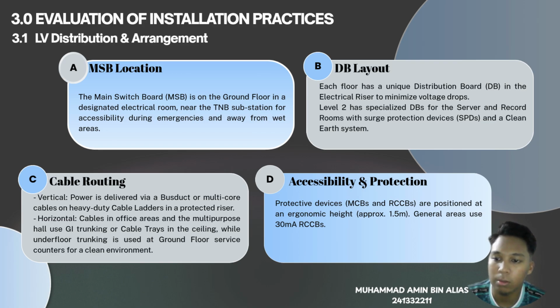After that is cable routing. There are 2 types of cable routing in this building, which are vertical cable routing and horizontal cable routing. The vertical cable routing is where the power is delivered from the MSB to the upper floor via bus duct or multi-core cables on heavy-duty cable ladders in a protected vertical riser. Meanwhile, the horizontal cable routing uses cables routed through galvanized iron trunking or cable trays that are concealed within the false ceiling, and it is usually used in office spaces and the multi-purpose hall.